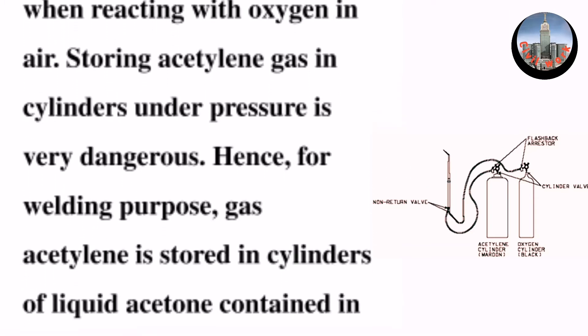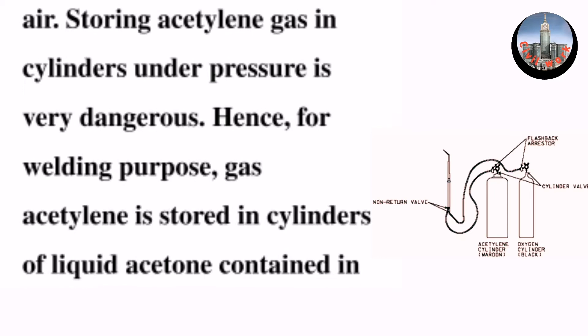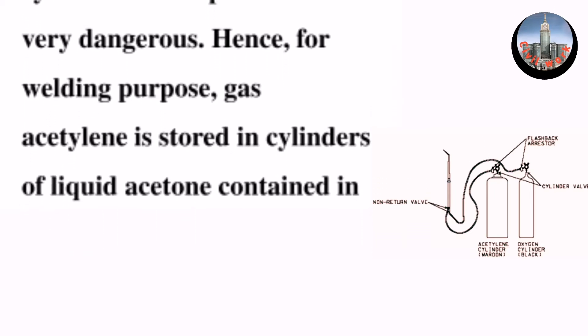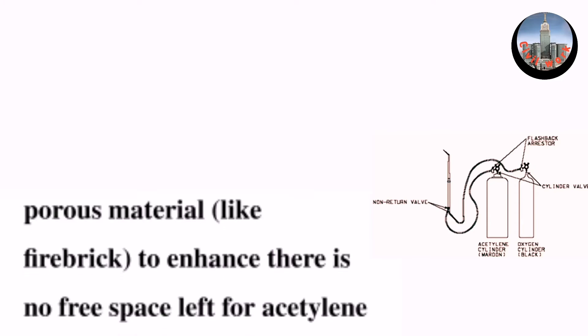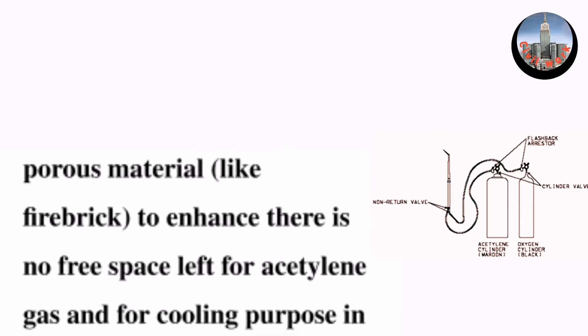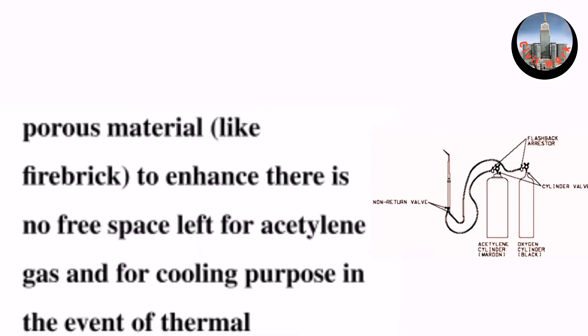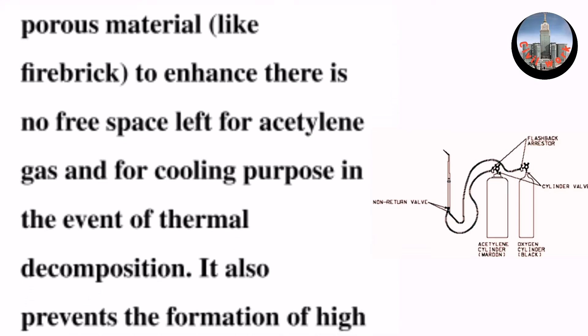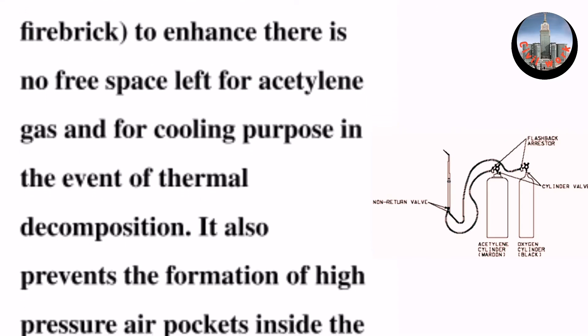Hence, for welding purposes, acetylene is stored in cylinders of liquid acetone contained in porous material like firebrick to ensure there is no free space left for acetylene gas and for cooling purposes in the event of thermal decomposition.